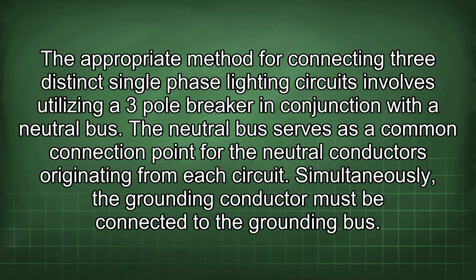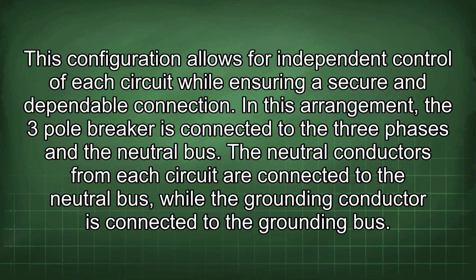The appropriate method for connecting three distinct single-phase lighting circuits involves utilizing a 3-pole breaker in conjunction with a neutral bus. The neutral bus serves as a common connection point for the neutral conductors originating from each circuit. Simultaneously, the grounding conductor must be connected to the grounding bus. This configuration allows for independent control of each circuit while ensuring a secure and dependable connection.